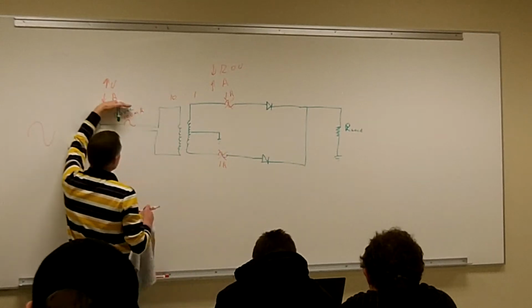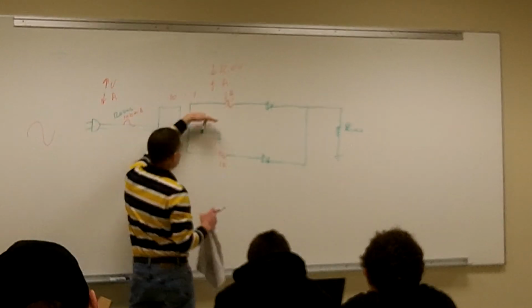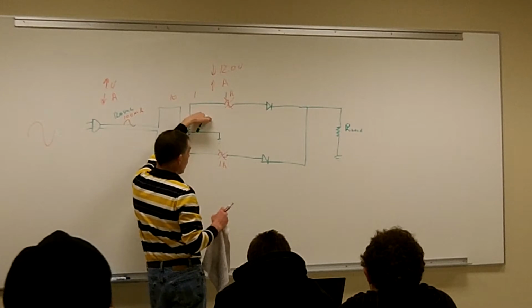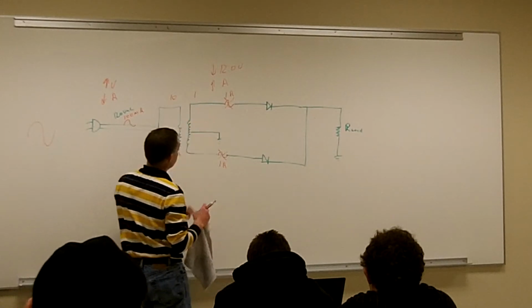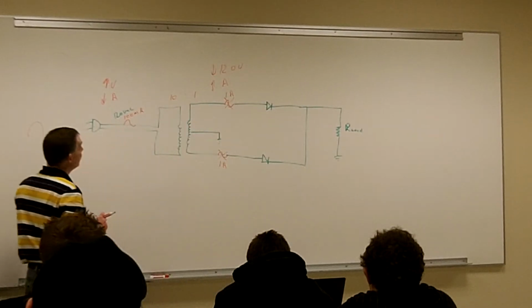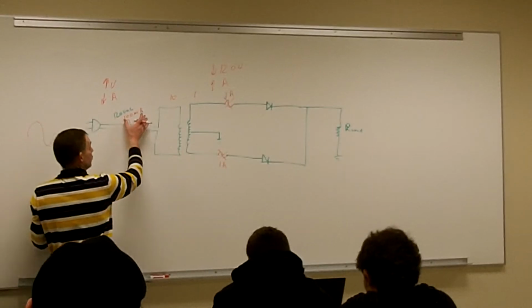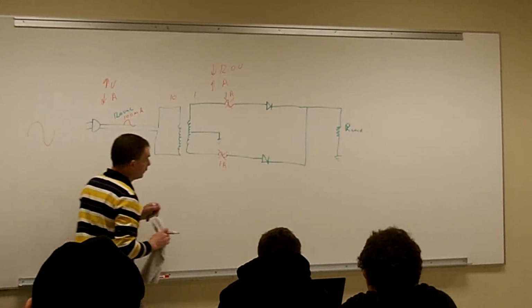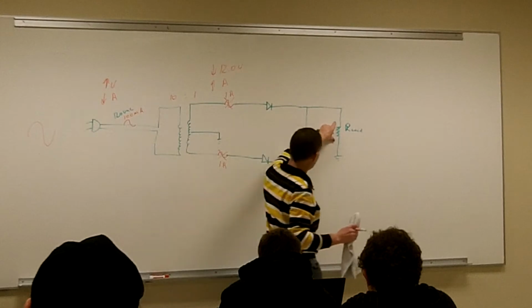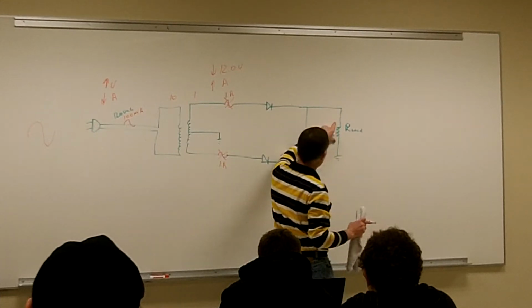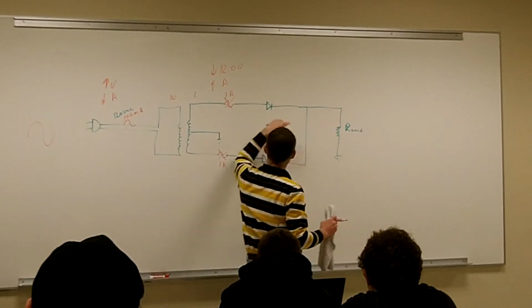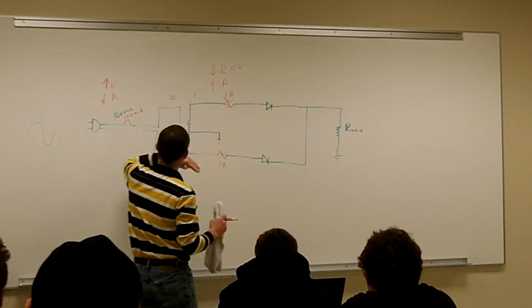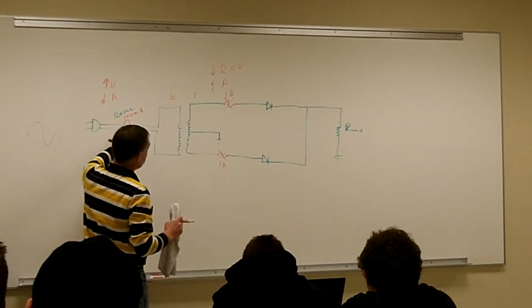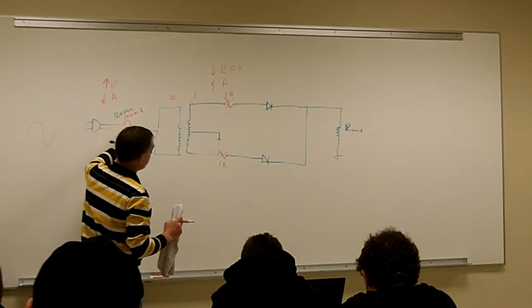So this 100 milliamp fuse will make sure the current going through our secondary will never exceed our 1 amp. Now a 100 milliamp fuse isn't very much, so it doesn't take much to short out your load or put in the wrong resistor, start drawing 1 amp of current on my secondary, and blow that 100 milliamp fuse on the primary.